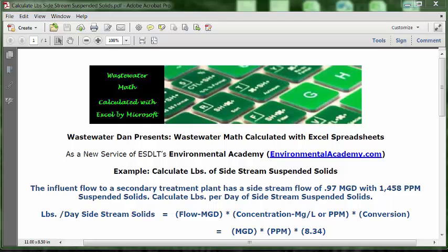And since we have flowing wastewater, I'm going to use the waste stream version of the poundage calculation formula, which has three elements. One element is fixed. That's the standard conversion factor from gallons to pounds, which is 8.34.